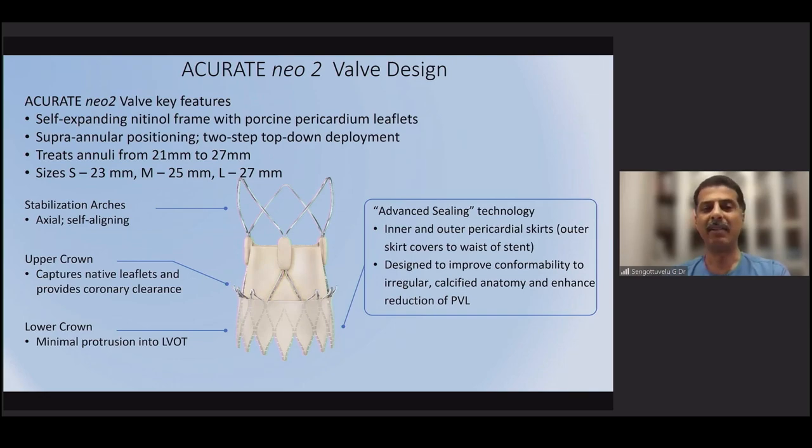It is a supra-annular valve, which gives it better hemodynamics. It uses a two-step, top-down deployment where the upper frame deploys first and then the lower portion opens. It comes in three sizes — small, medium, and large — and can treat annulus sizes from 21 to 27 millimeters.